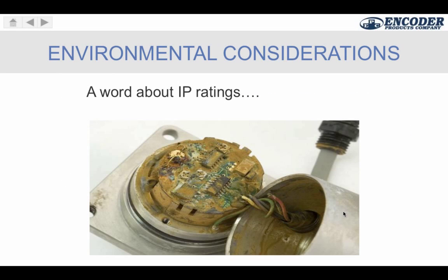In addition to the electrical features, we also want to give some attention to environmental considerations and IP ratings. Here we see an example of an encoder that was subject to conditions that exceeded its environmental ratings. In this particular case, the liquid, the solvents, I think it was, worked its way down through the connector into the housing and had the impact that you see here.